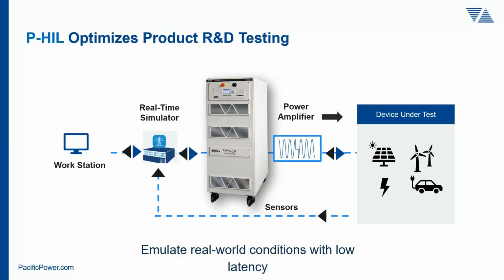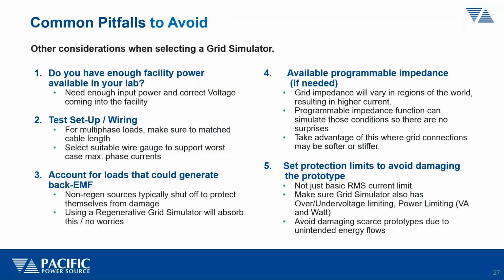So in conclusion, let's look at a couple of other things to summarize some pitfalls to avoid in making your selection. The first is you need to have enough power in your lab. Check what kind of facility power you have available to see what kind of grid simulator you can support. Obviously, a lot of these are higher power, so they require 3-phase power. In the US, that can be 208 or 480 volts; in other parts of the world it's generally 400, 380 to 415.